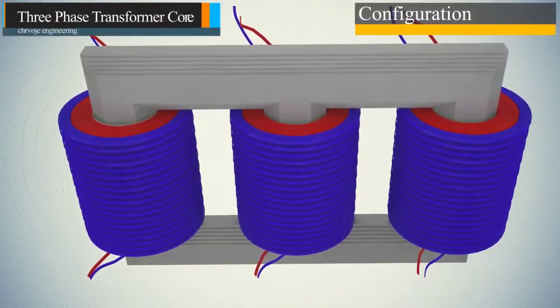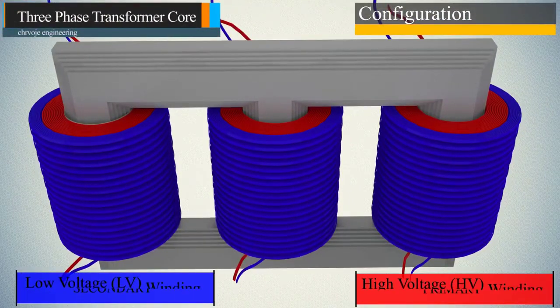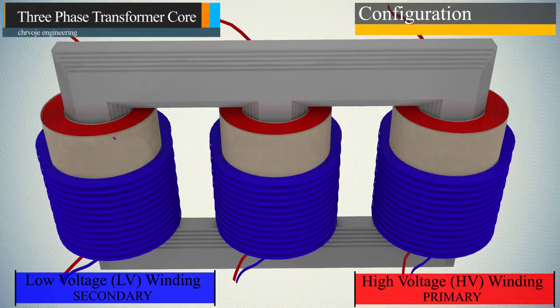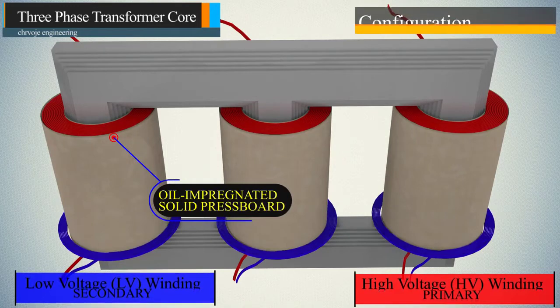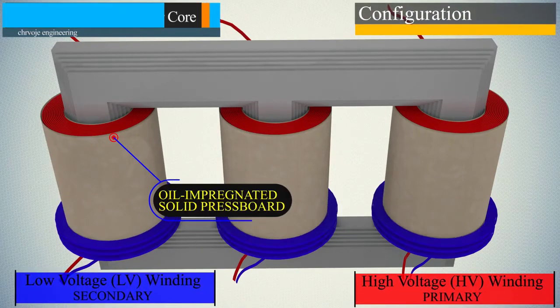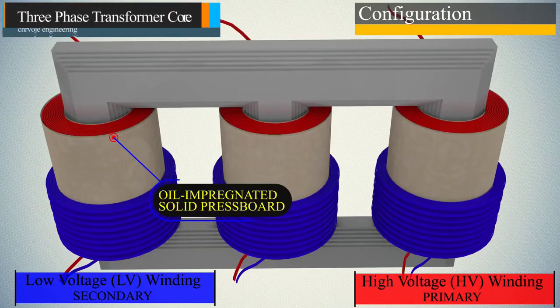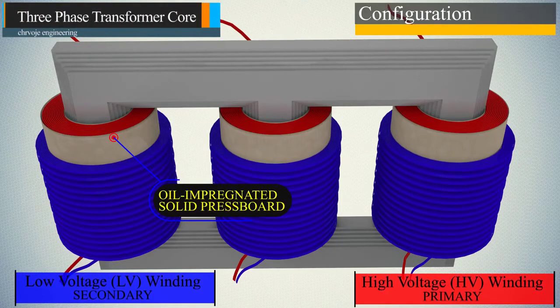Secondary winding sits concentrically around primary winding. Also, we must mention that there is insulation, oil-impregnated solid pressboard, between primary windings and secondary windings. Insulation is needed to prevent physical contact between the windings and short-circuit fault.